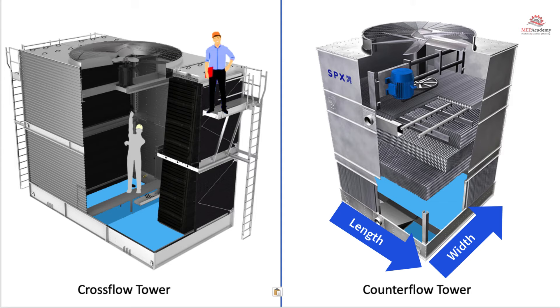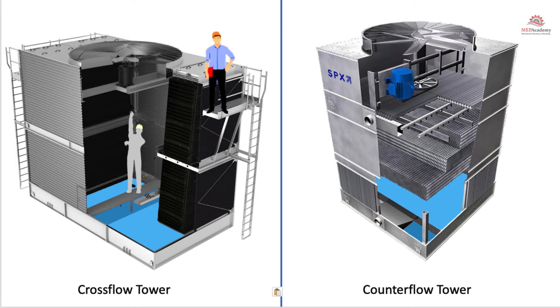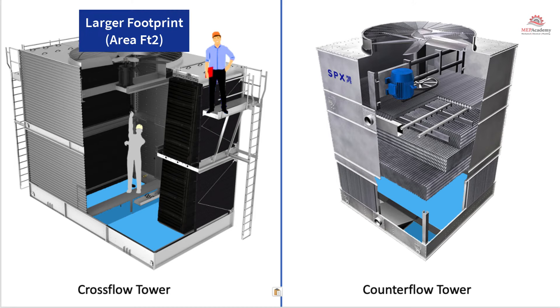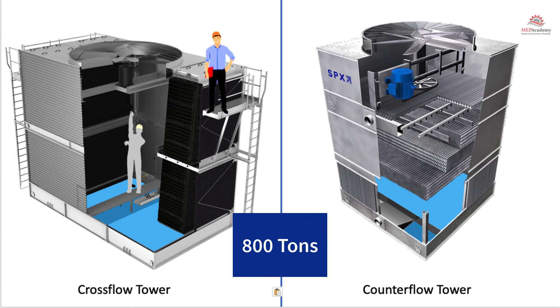The counter flow for the same tonnage is going to be taller. When figuring out where to put the tower, you have to look at the physical area of the space, how the air can move around, and what walls may be in the way. Because of the larger footprint of the cross flow tower, its operating weight and shipping weight are often more and it may also require additional structural support legs. At around 800 tons, the footprint area differences between counter flow and cross flow can change.